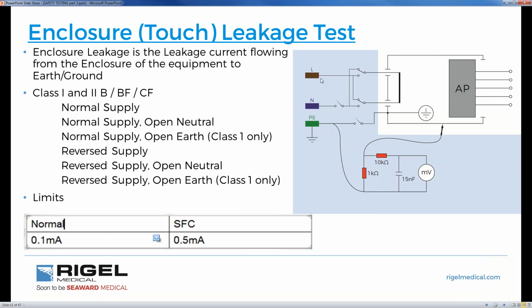So if we had 230 volts and we had our system, and I'll use the same example throughout the presentation, let's say the system current consumption is 100 milliamps, we have 99 milliamps flowing between live and neutral. Well, 1 milliamp is in the system somewhere, escaping through stray capacitance and dielectric resistance. If we open the earth, which is one of the single fault conditions, then the leakage will flow through the body model back to protective earth. So effectively what we're simulating is a means of operator protection, to clarify how much current would flow through a person if they were to touch a metallic chassis or an accessible conductive part if the protective earth was open.